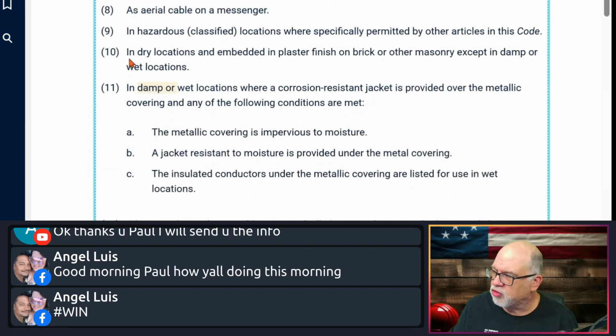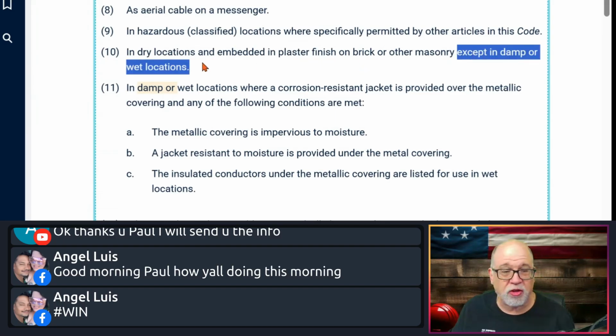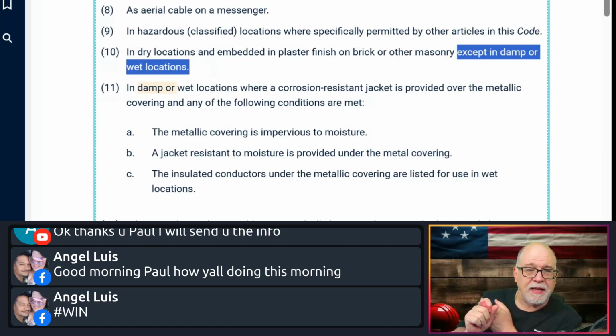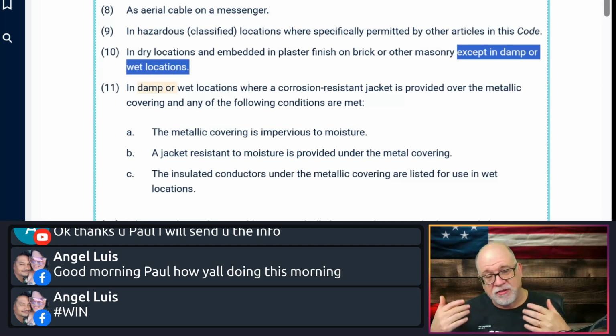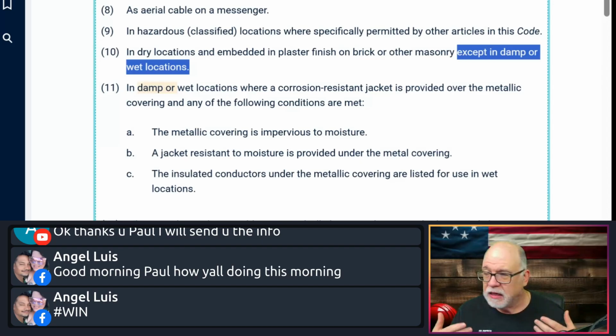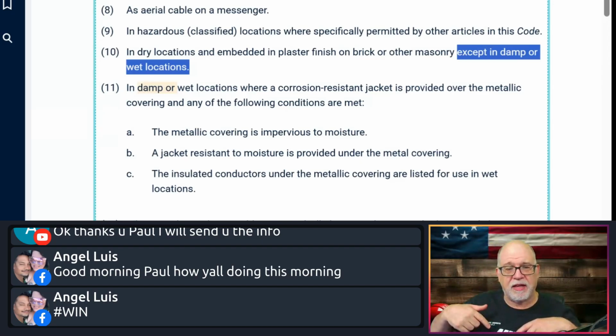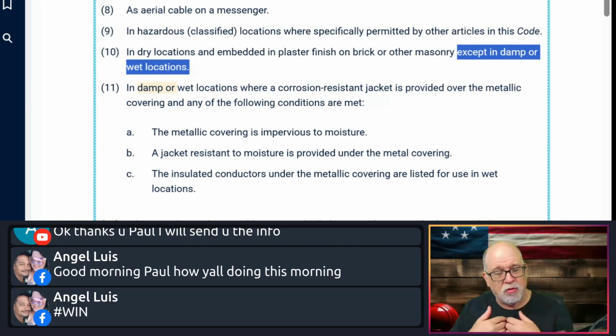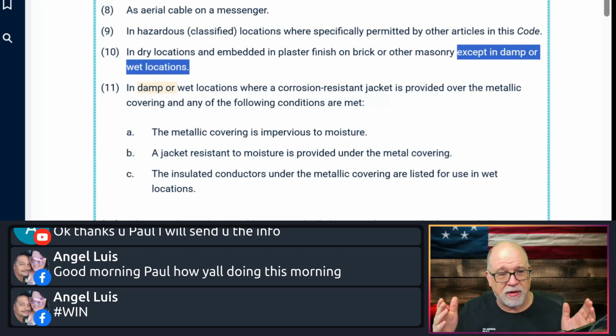10, it says in dry locations and embedded in plaster finish on brick or other masonry except in damp or wet locations. So the question we get from people all the time is, can MC cable be embedded in plaster finish on brick or other masonry? Yes, as long as the brick or masonry itself is not in a wet location or subject to those types of conditions, then it's perfectly fine. And we'll see some other caveats in a minute where the use is not permitted kick in. But yeah, dry location inherently, you can use MC wherever you want in a dry location.